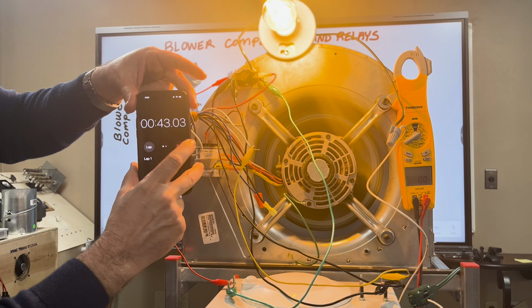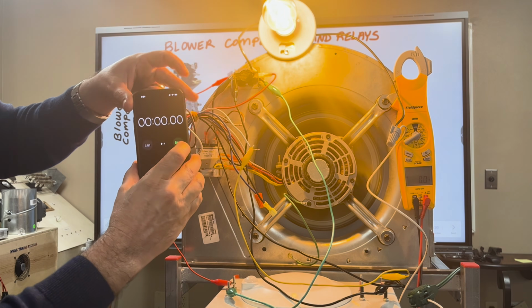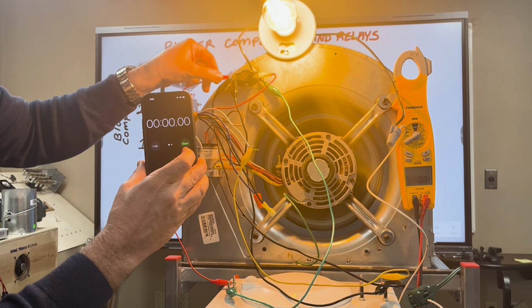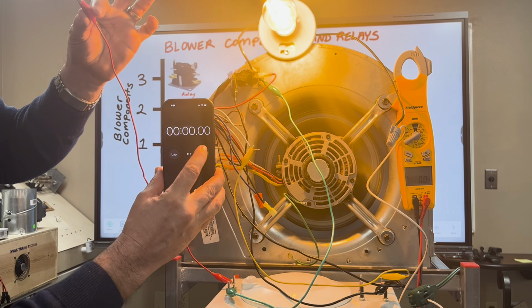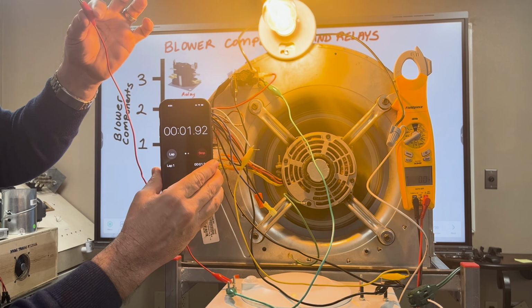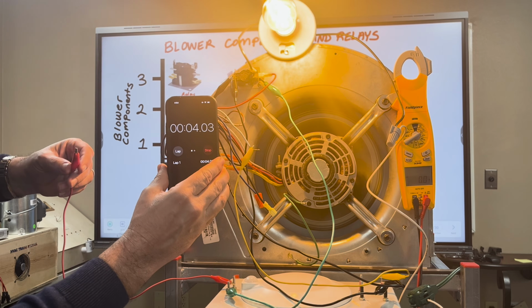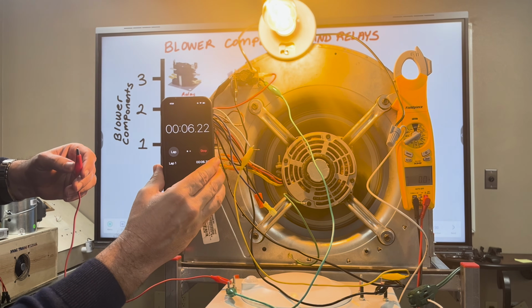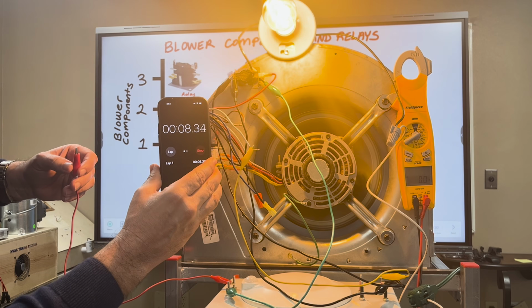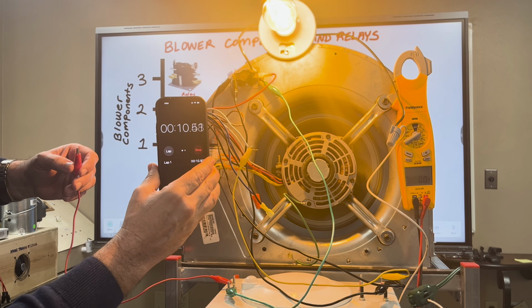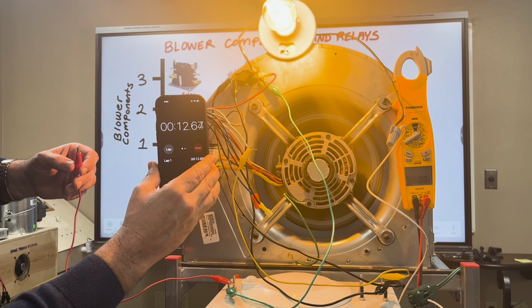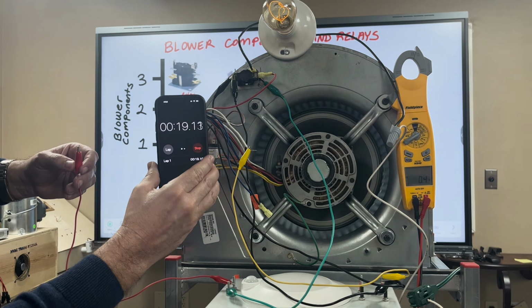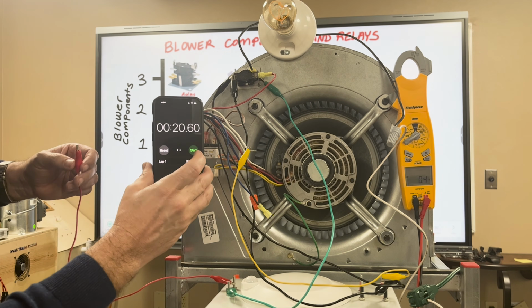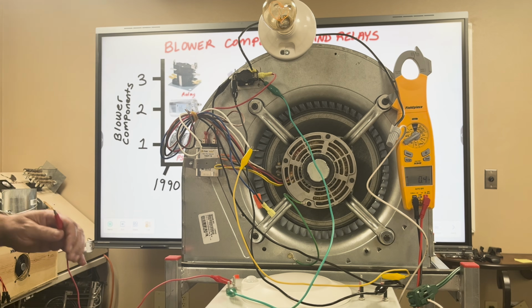Now we're going to hit stop or reset, and cool the relay down by removing 24 volts, to see how long it takes to break contact on both poles. Okay, 13 seconds for the fan motor to turn off, 18 seconds for the light to turn off.